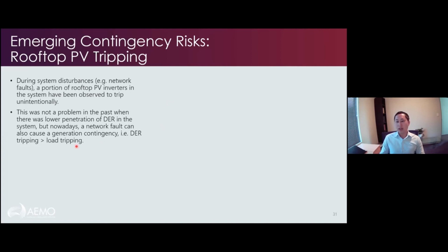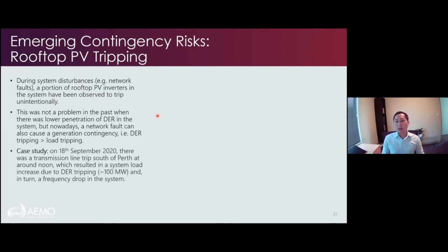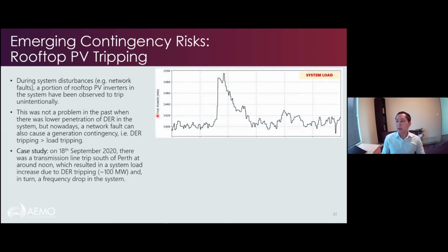So the amount of DER tripping is exceeding the amount of load tripping. Usually what we saw in the past is that with a network fault, you get a load rejection event. So you lose load as a result of voltage disturbances. But now we're losing load and DER in the middle of the day, and actually DER is greater than the load that we're losing. And so here's a case study from the 18th of September. There was a transmission line trip on the 132 kV system south of Perth around noon, and it caused the system load to increase by 100 megawatts due to the DER tripping. So here it is.